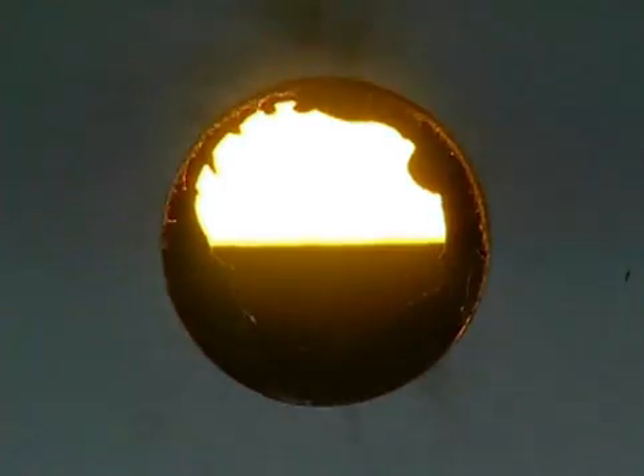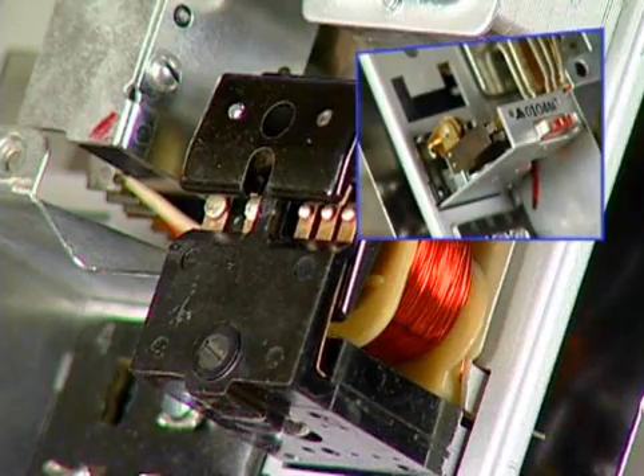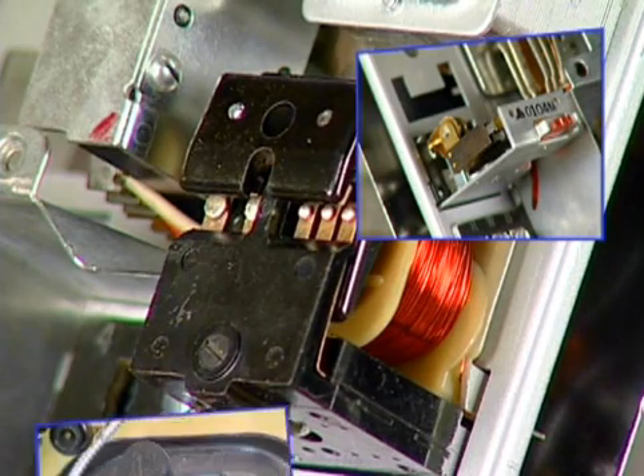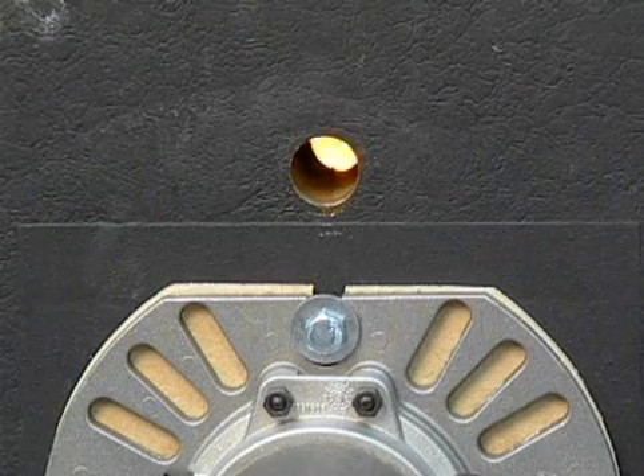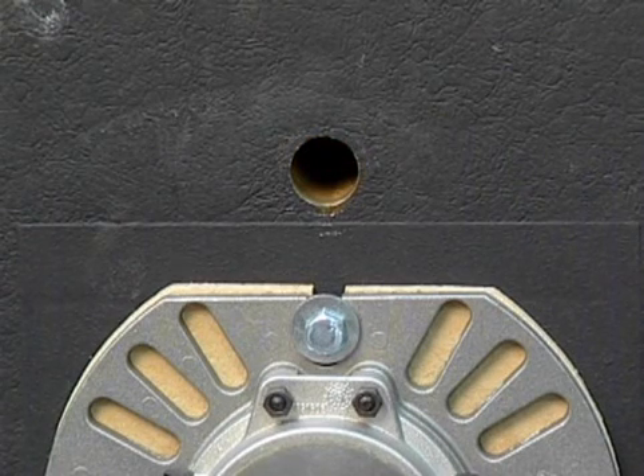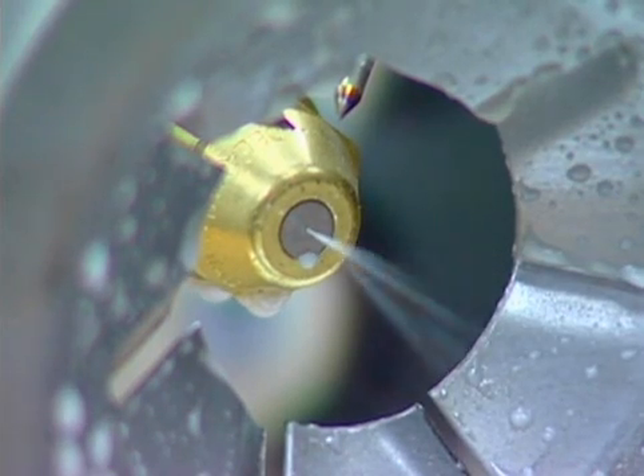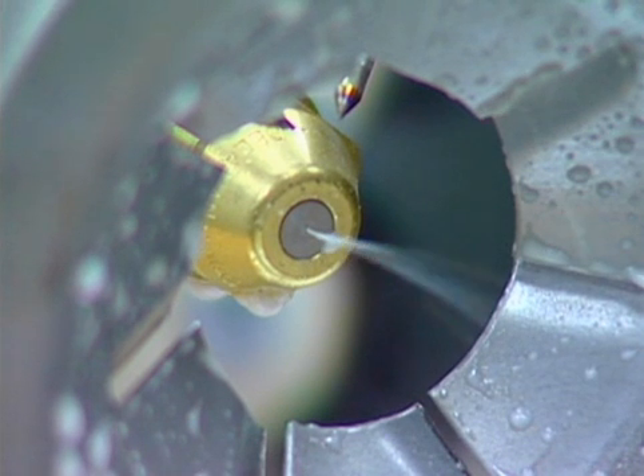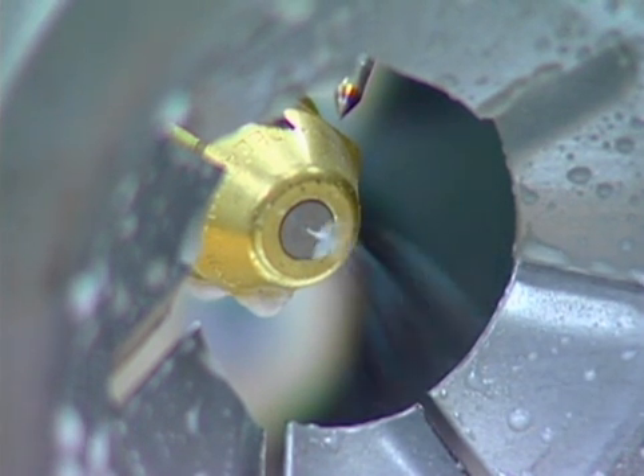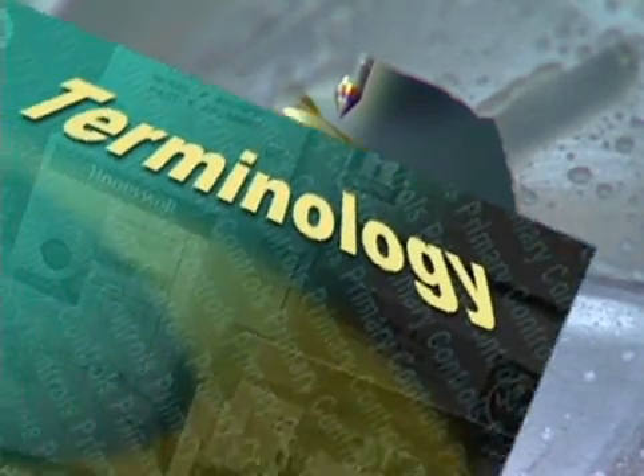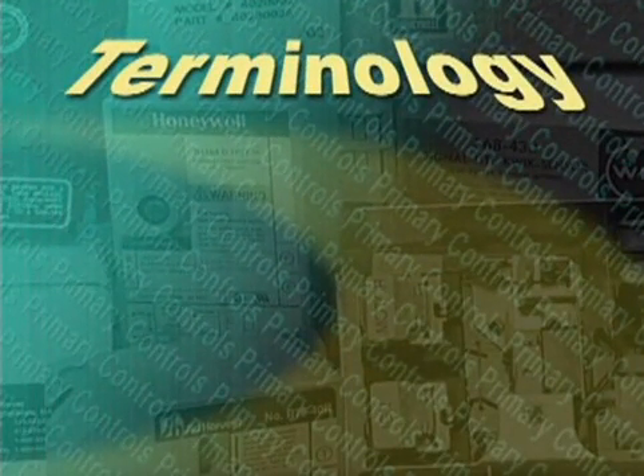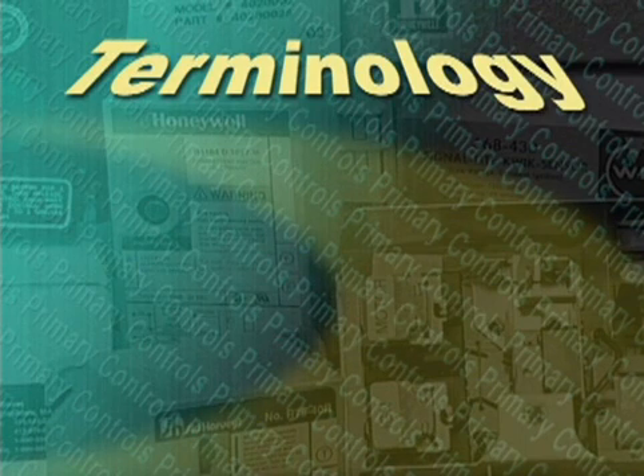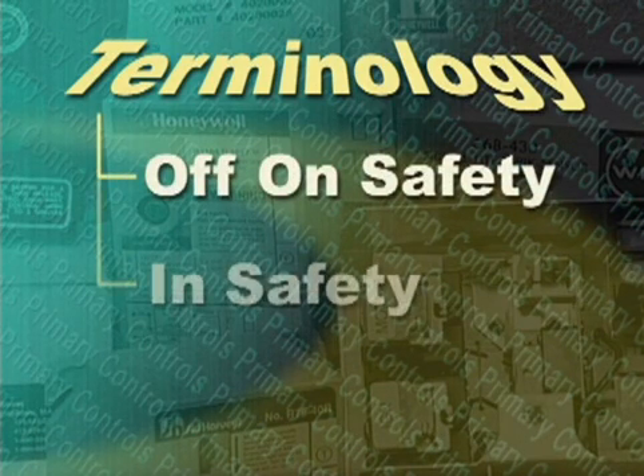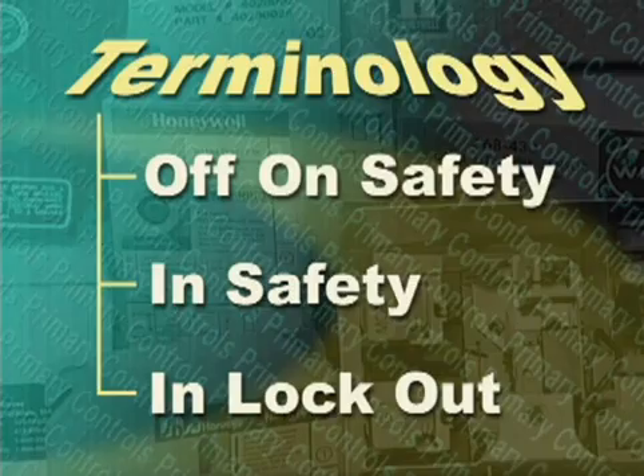It is also critically important that primary controls react quickly to the presence or absence of flame while the oil burner is running. The primary control must shut the burner off promptly if no flame is established on startup, or if the flame is lost during the run cycle. If the primary control did not shut off the oil burner in these circumstances, the burner could continue to pump fuel into the unit, creating hazardous conditions. When the primary control shuts off the burner because no flame is sensed, this condition is referred to as being off on safety, in safety, or in lockout.